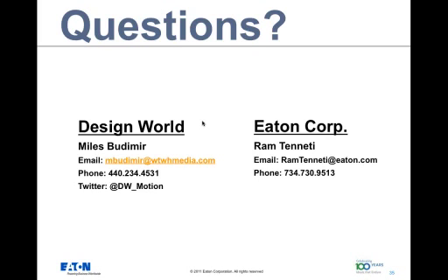Yes, the answer is yes, and we do that. Okay. And one more question from him: what is the price difference between a regular starter versus a soft starter? Again, it depends on the chart I referred to before for someone else's question. If you're not looking for too many frills and you're using the basic soft starter, the price difference can be about 5 to 10%, with the soft starter being higher compared to across the line. But if you're looking at a soft starter with all the frills that are needed, then the cost is going to increase from there. But for the low-end soft starter, which still provides smooth ramp up without too many frills, the cost difference can be as little as 5%. Okay, that sounds good.